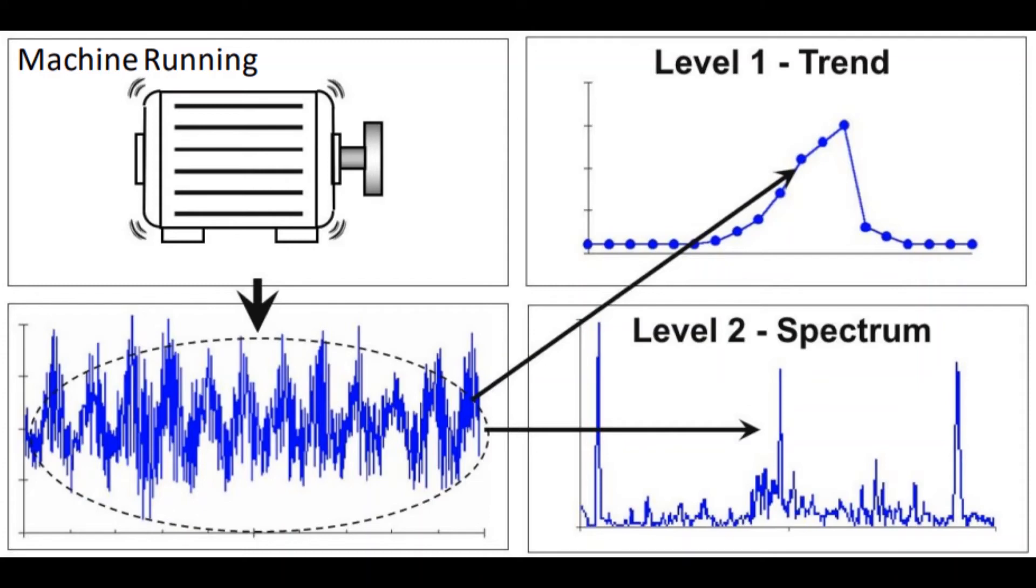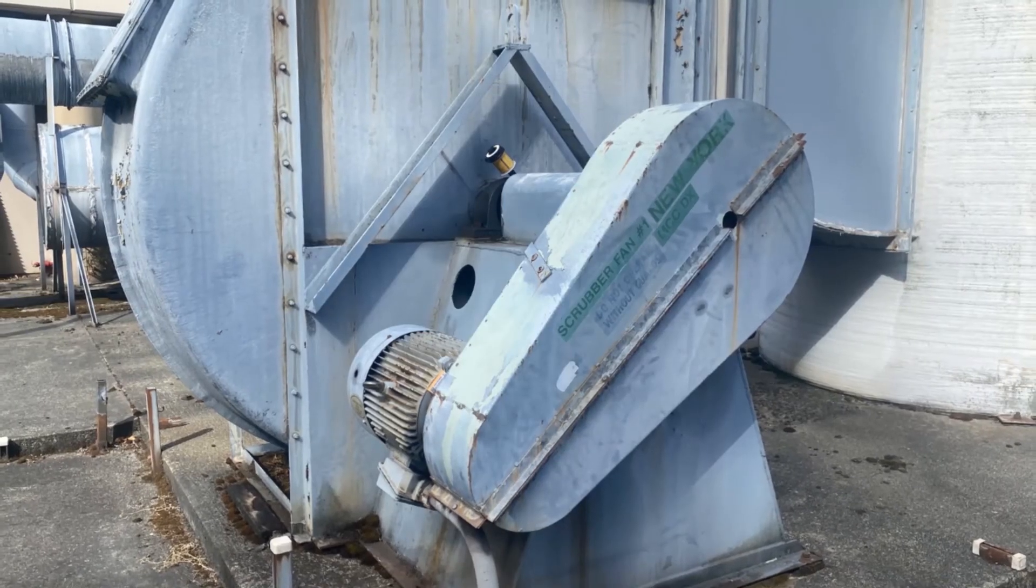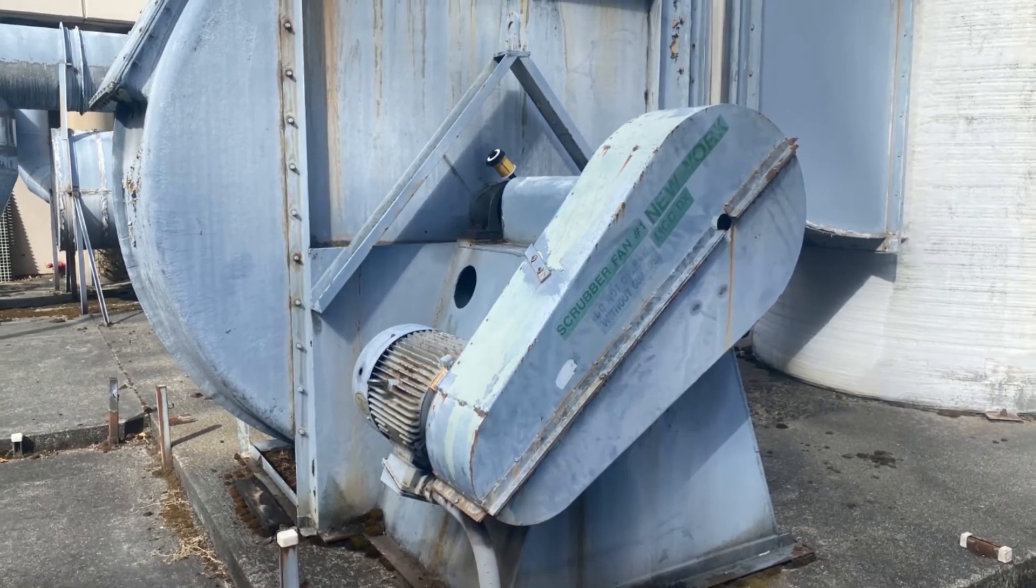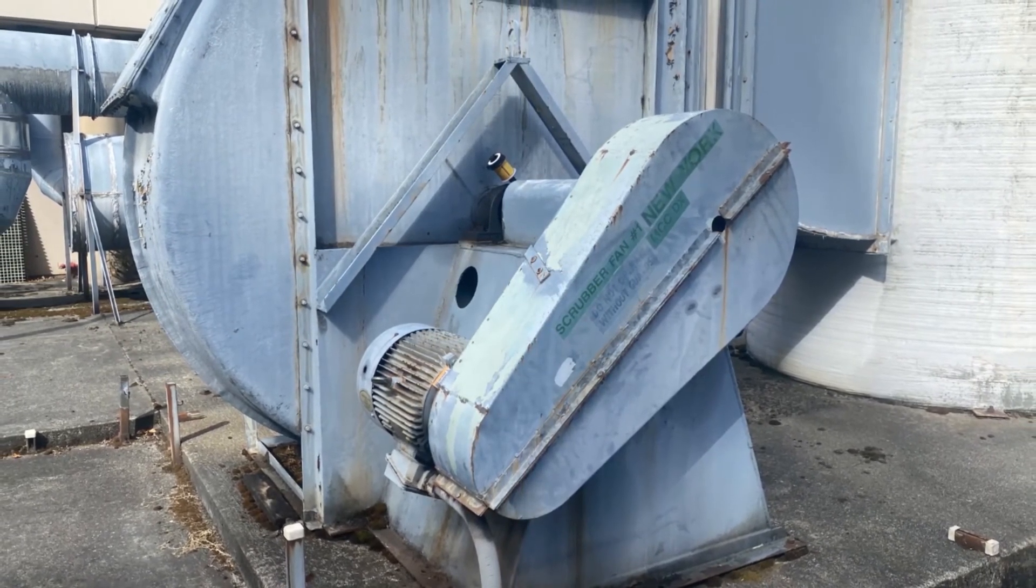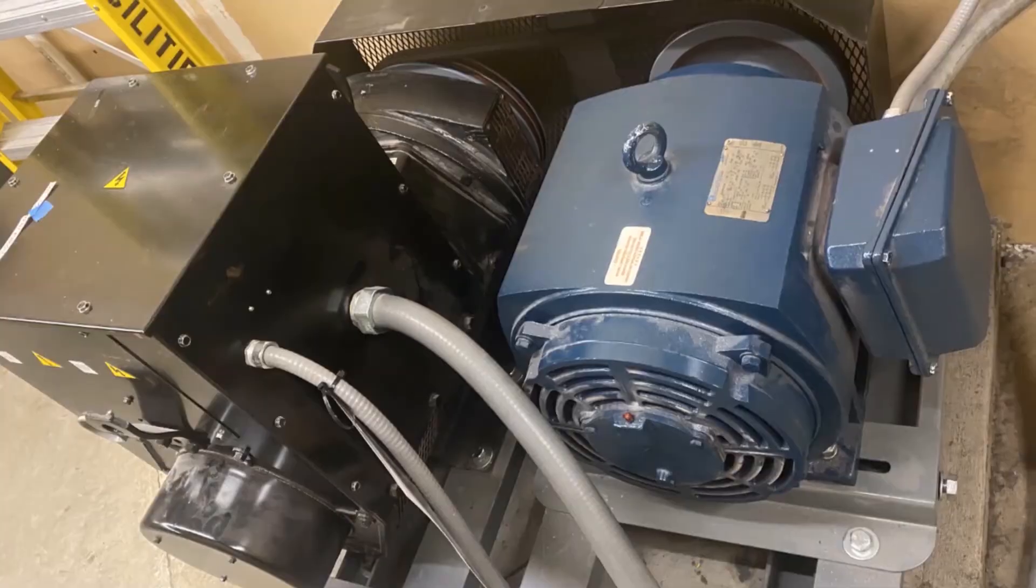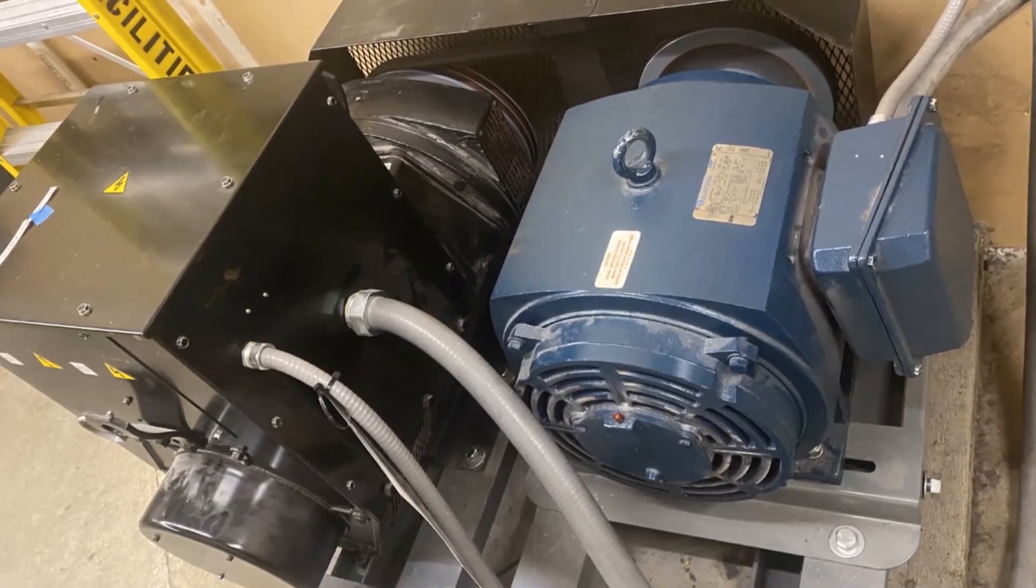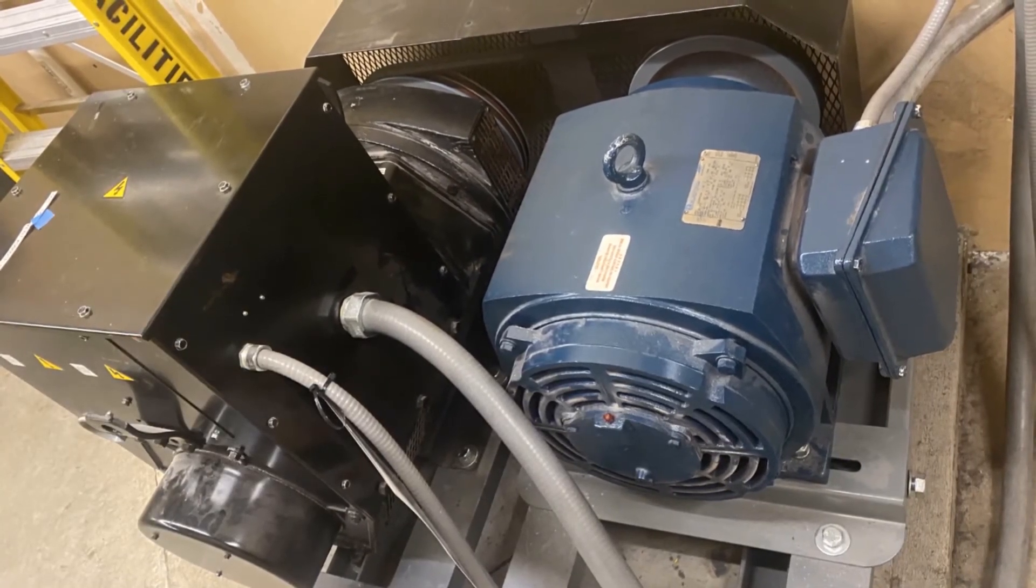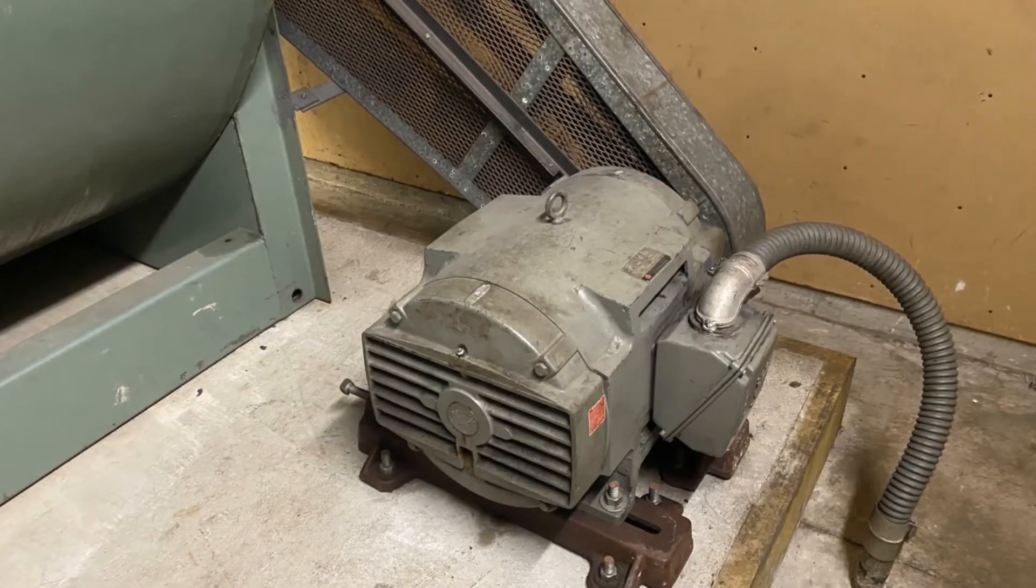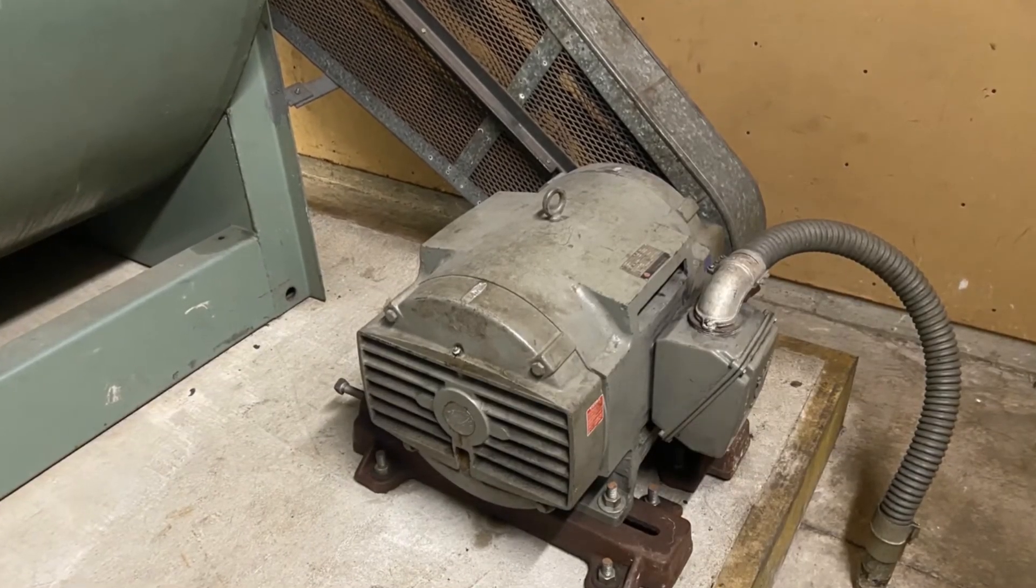Reviewing the vibration results: when to wait, when to act, what to do. Many think that high vibration means that something needs to be fixed immediately, but that is often not the case. Just because the vibration is high doesn't mean that there is a fault. All machines have vibration, and vibration can come from many different sources.